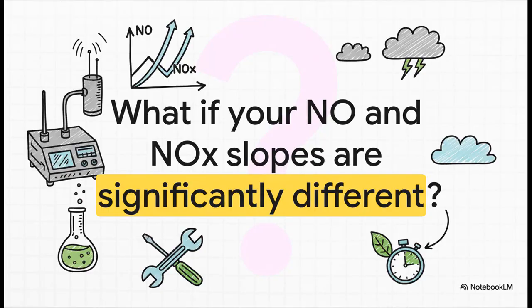Okay, let's talk about a classic problem you might see. You finish the calibration, you go into the diagnostics menu to check your work, and you see that the slope for NO and the slope for total NOx are way different. What's going on?